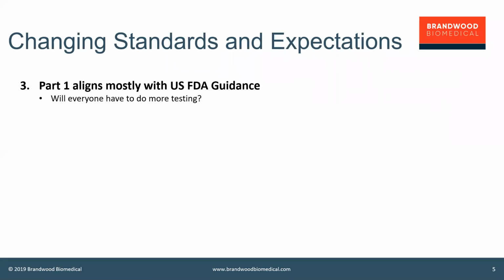What those ticks in the boxes in that table are about is what you have to think about for your particular device. So it's giving you a guidance as to what matters. FDA has always been visibly more conservative about that, wanted people to think about more things than were ticked in the standard. And so FDA have had in their guidance a modified table A1 with some extra boxes ticked.